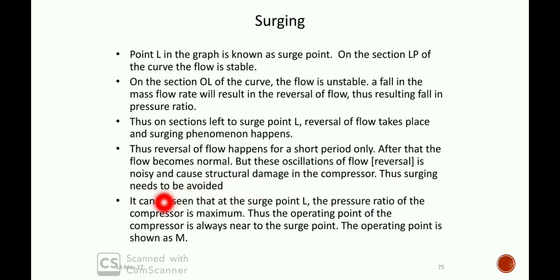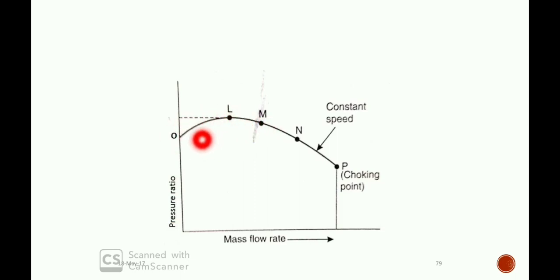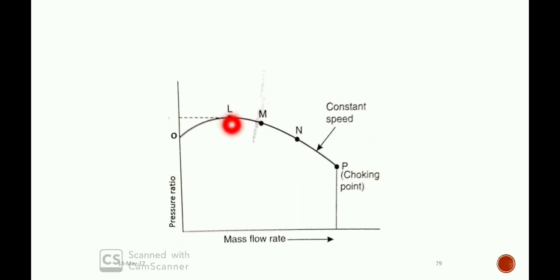Surging needs to be avoided. The best design operating condition will be at either point M or N, which will be closer to the surge point but should not fall below the surge point. The operating condition of the compressor should not fall below the surging point.